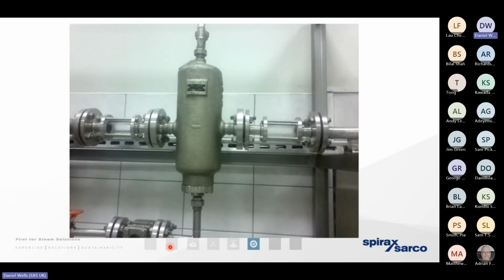Now, quite often, along with pressure gauges, steam separators are value engineered. They may be designed in at the design stage, but they're highly likely to be removed by the installing contractor or the client at the project installation stage. When that happens, the steam is going to be wetter. So that's when those mechanical issues and those inefficiencies start to creep back in. The good news is they can be retro-engineered back in very, very quickly.